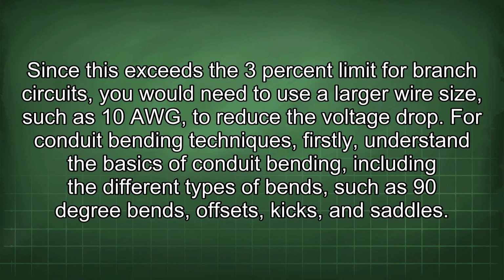Since this exceeds the 3% limit for branch circuits, you would need to use a larger wire size, such as 10 AWG, to reduce the voltage drop.